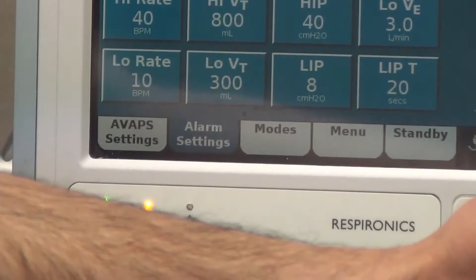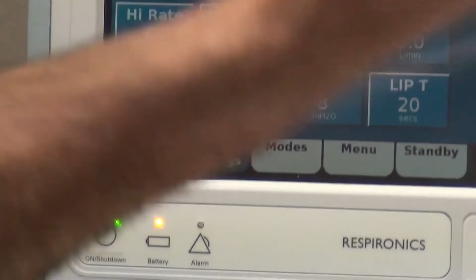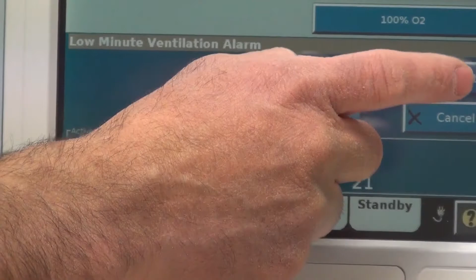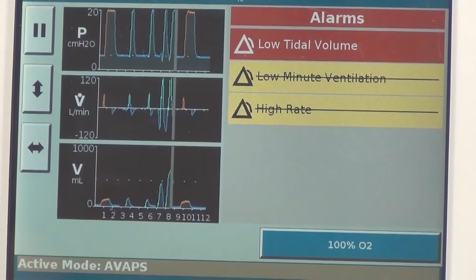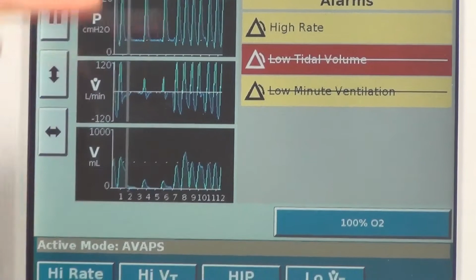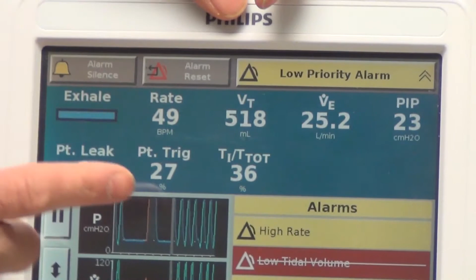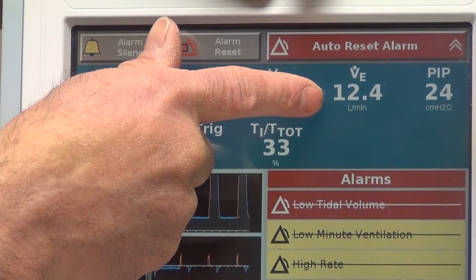Right here you have low minute ventilation alarm, which is on the other machine, the 840, you set a high number and low number. On the LTV, you would set just the low number. Just like the LTV, on this machine you would set just the low alarm, which we were setting at 18 for a high and then a 3 for a low. And again, this one's already set to low. And notice if we look at the alarm, since it says low tidal volume, again, I've been moving the tube around as we're going. And now it's going to give me a higher rate because I'm making it breathe really fast. And you can look at the top of the screen, you can see the respiratory rate, the tidal volume, the minute ventilation, and the peak inspiratory pressure.